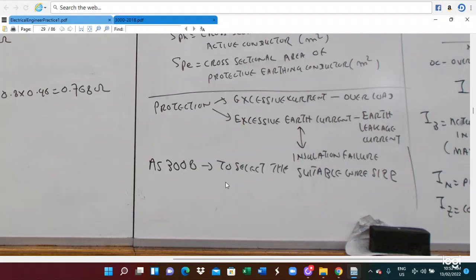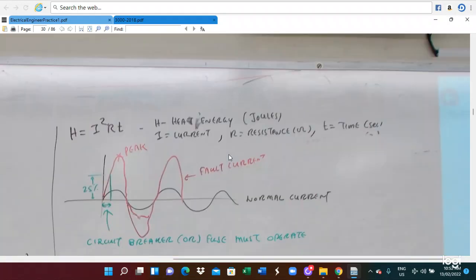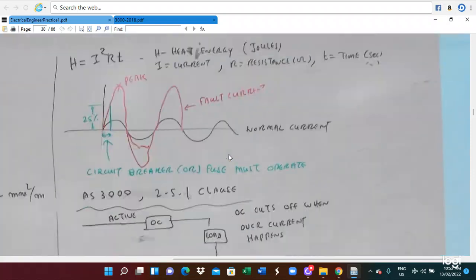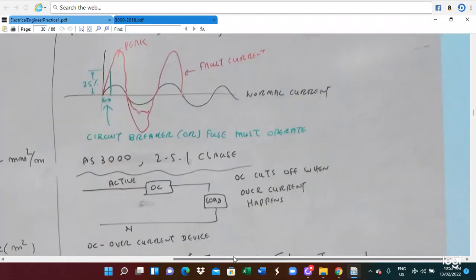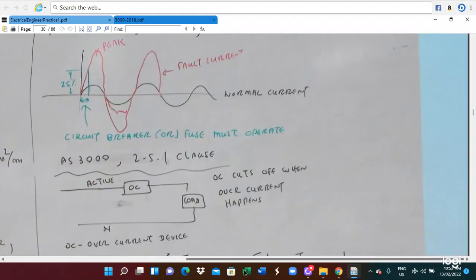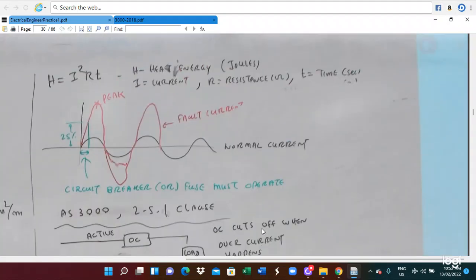So therefore, in this case, to select the appropriate cable size, we have to utilize the AS3008 rule to select the suitable cable size. So this is how to select the cable size and how to select how long you should run the cable in the whole circuit. We calculate by this way.